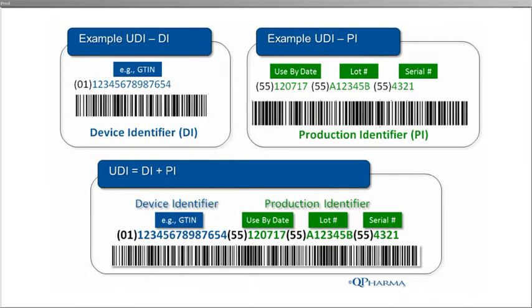A UDI is created by bringing together two parts: the device identifier in blue and the production identifier in green. It is important to remember that a UDI will require both of the above pieces. These can be concatenated into one long barcode, or be split over two smaller barcodes.